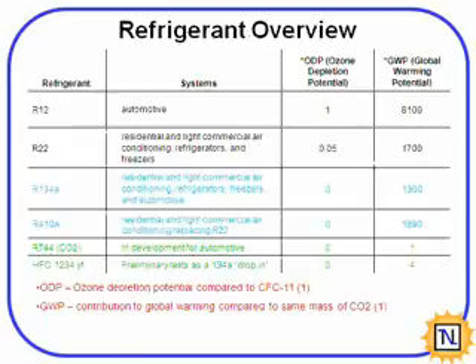Another important consideration, since it is a refrigerant-based system, is what kind of refrigerants go in. And this is kind of a snapshot of the history of refrigerants. R12 and R22 really aren't around much anymore. R22 you still see a bit of as they're trying to get rid of these systems as they're phasing out. Both of these have some ozone depletion and then fairly high global warming potential.